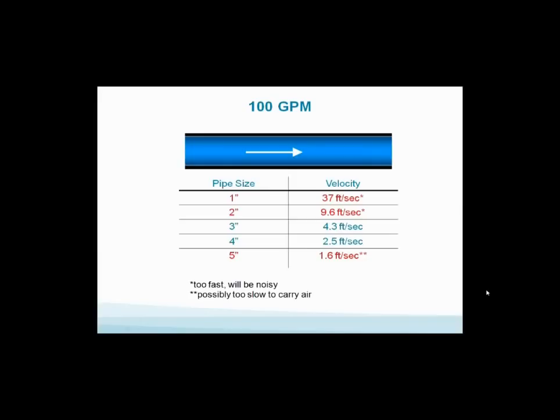What's wrong with a five inch pipe? The velocity is 1.6 feet per second - is there anything wrong with that? Yes, it may not be able to move air. There's a minimum velocity required per ASHRAE to be able to move air around your system and get it to your air separators and get it under control.